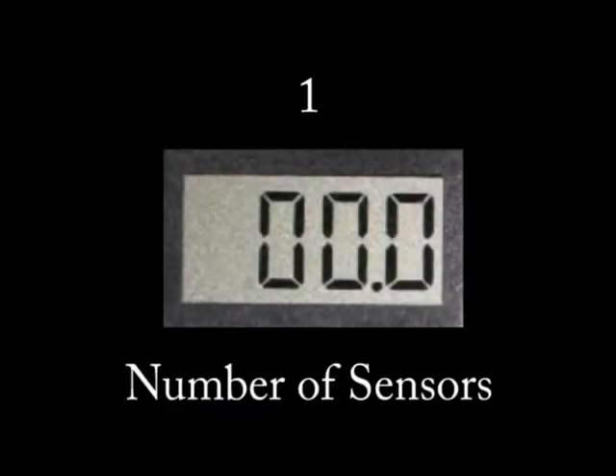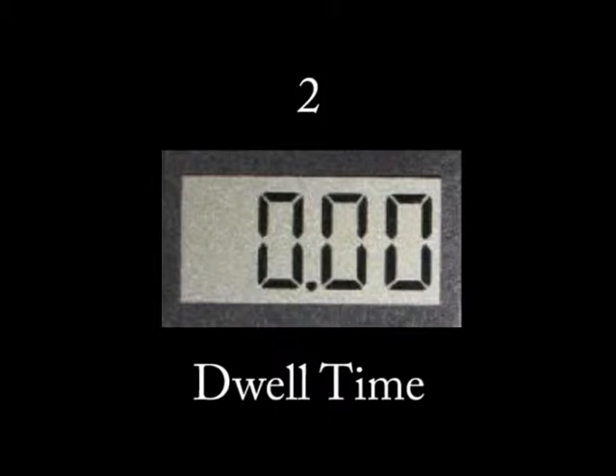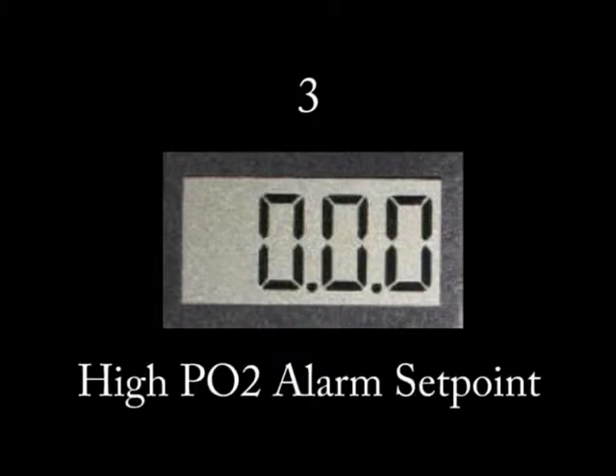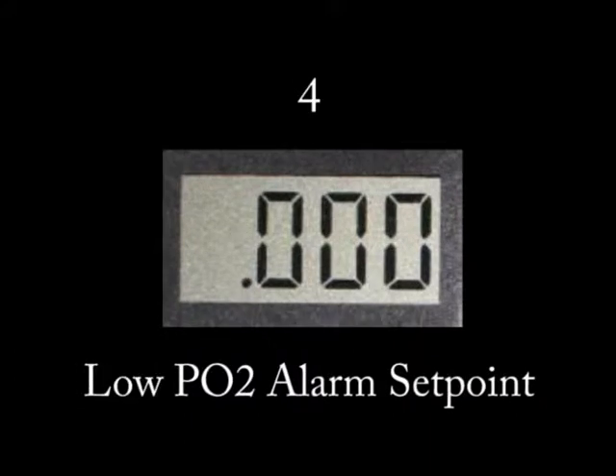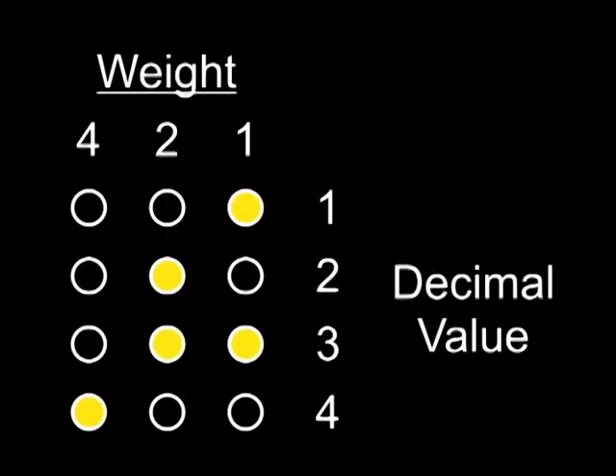Step one is to change the number of sensors attached to the display board. Step two is to modify the amount of dwell time between displaying subsequent sensor readings. Step three is to change the high PO2 alarm set point, and step four is to change the low PO2 alarm set point. Astute electronic types will note that the decimal point position can be interpreted as a binary value which reflects the number of the menu step we're at. This format is used often as part of the Gorilla Diving Products PO2 monitor system.